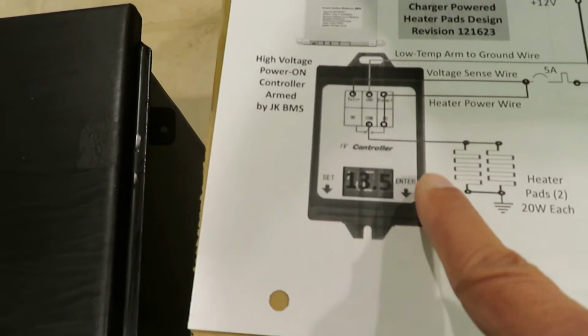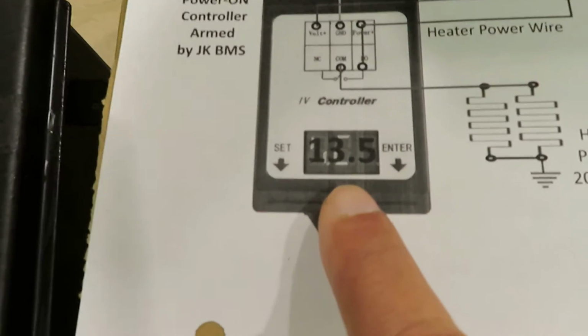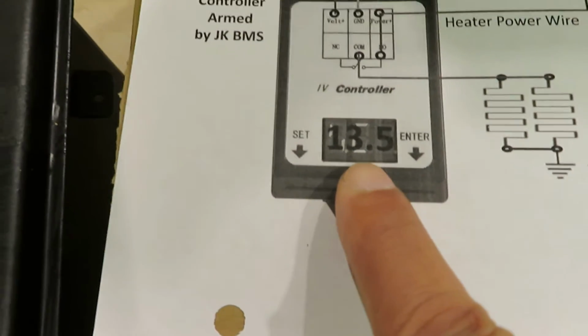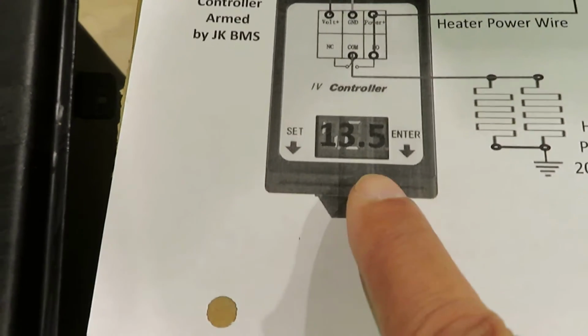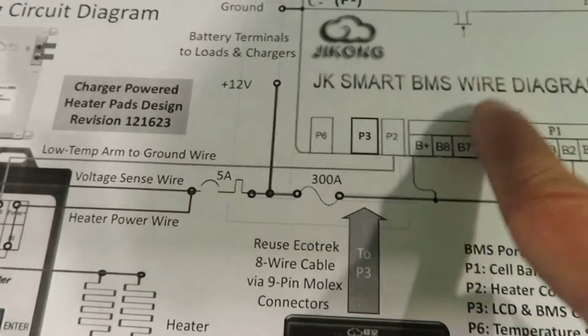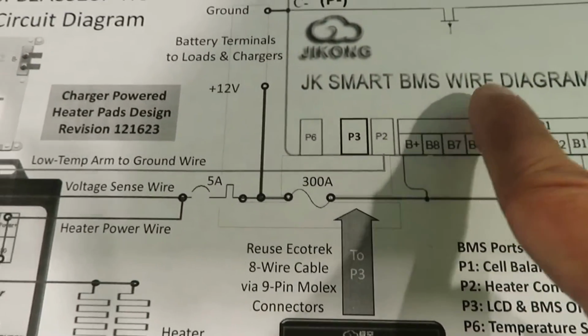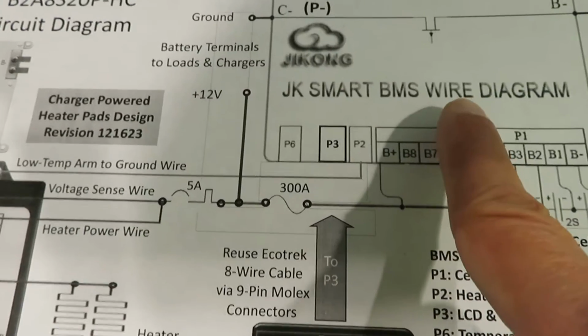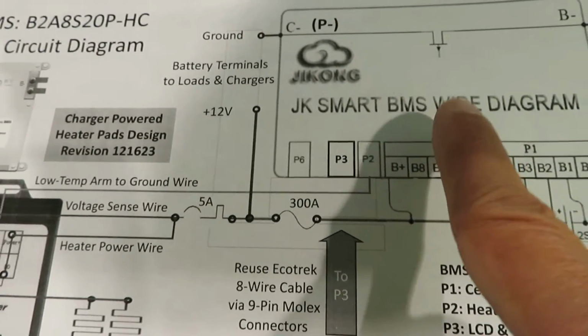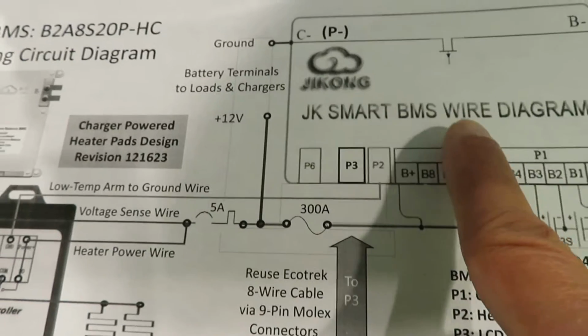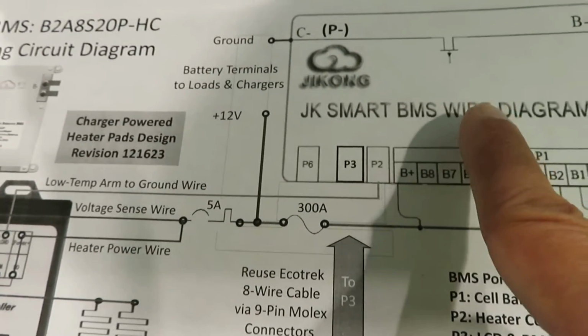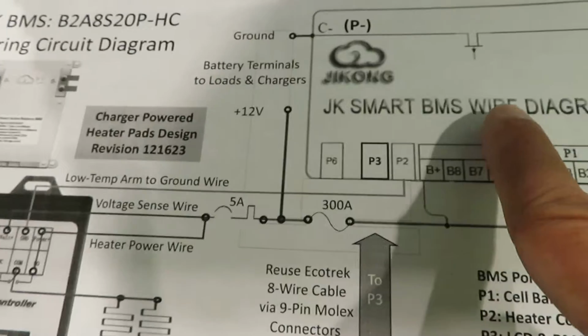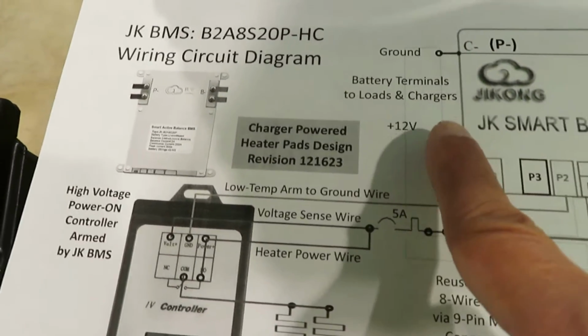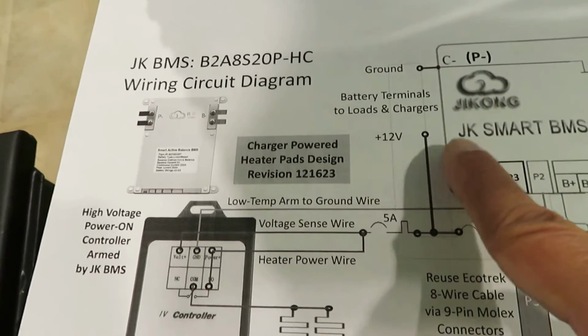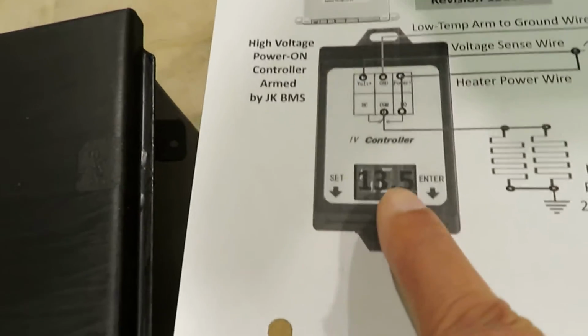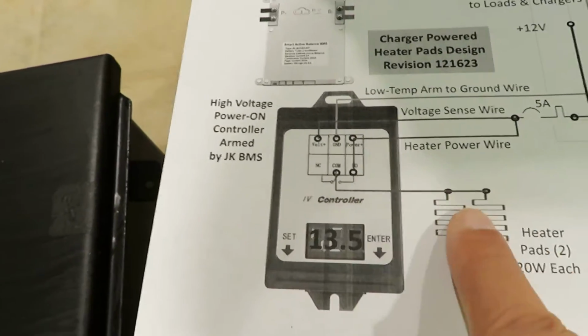This is programmed to turn on at 13.5 volts and turn off at 13.4 volts. If the battery is higher than 13.4 volts, it will draw down the battery first. Typically 13.4 is almost like a 98% state of charge, so it only draws down very little, not a whole lot, until it sees an external power supply or charging source higher than 13.5 before turning on the heater.